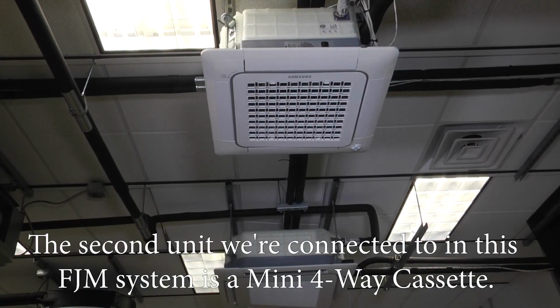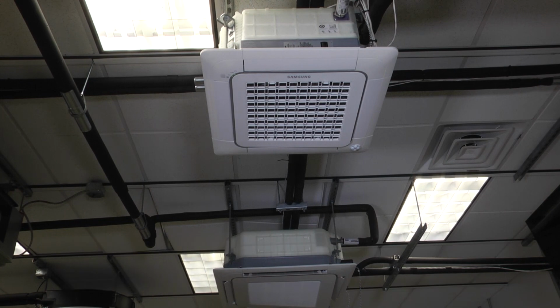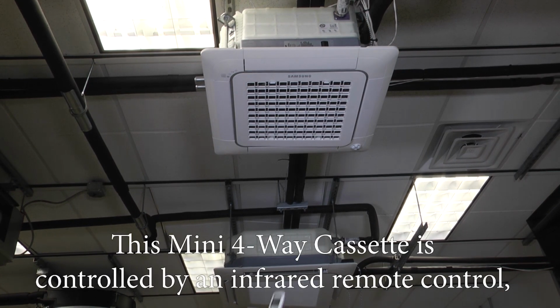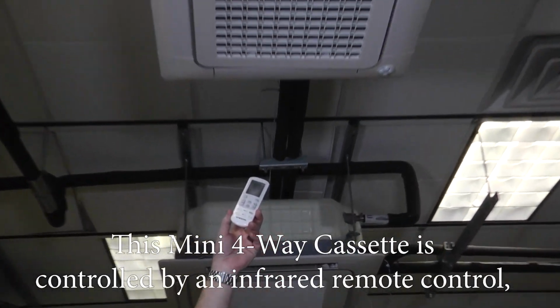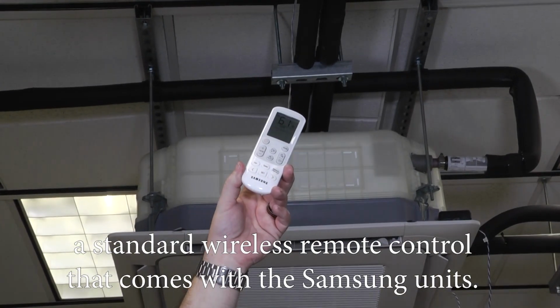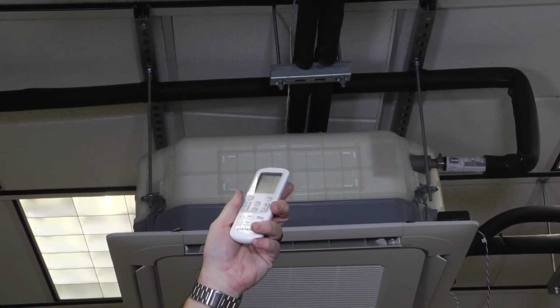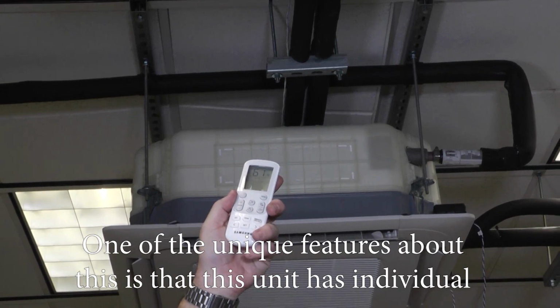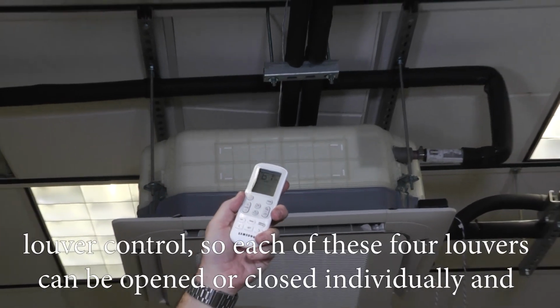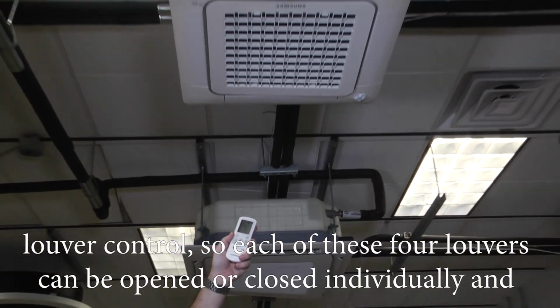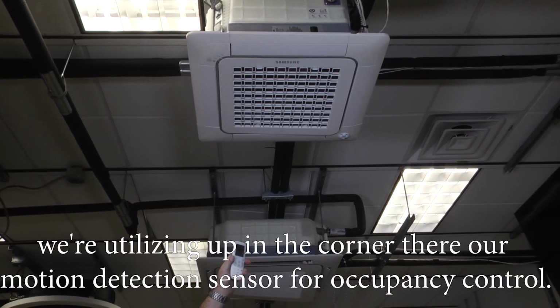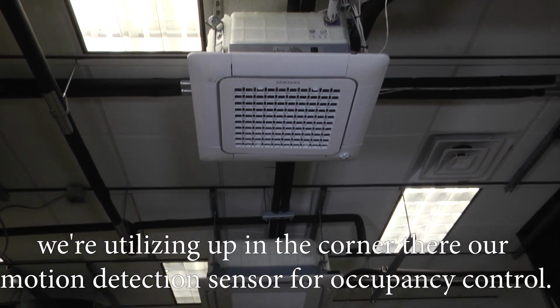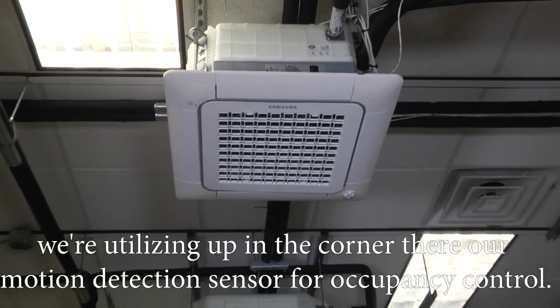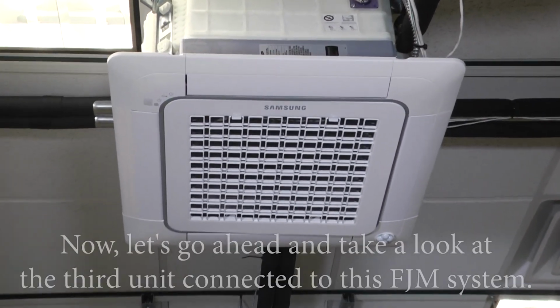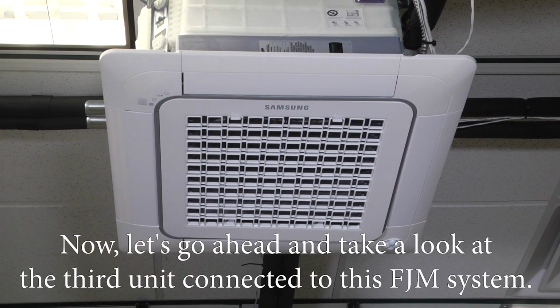The second unit we're connected to in this FJM system is a mini 4-way cassette. This mini 4-way cassette is controlled by an infrared remote control, a standard wireless remote control that comes with the Samsung units. And one of the unique features about this is this unit has individual louver control, so each of these 4 louvers can be opened or closed individually, and we're utilizing up in the corner there our motion detection sensor for occupancy control. Now let's go ahead and take a look at the third unit connected to this FJM system.